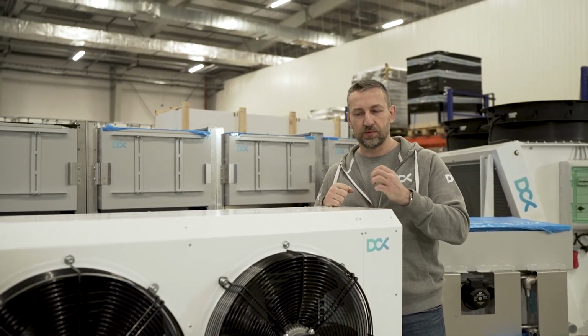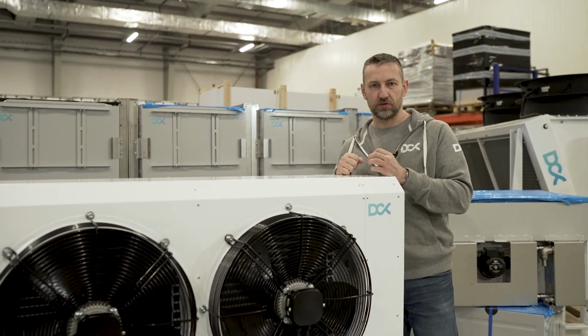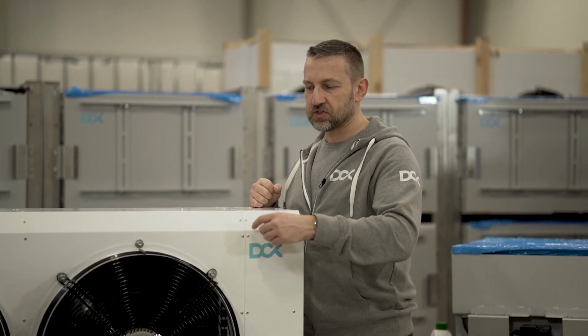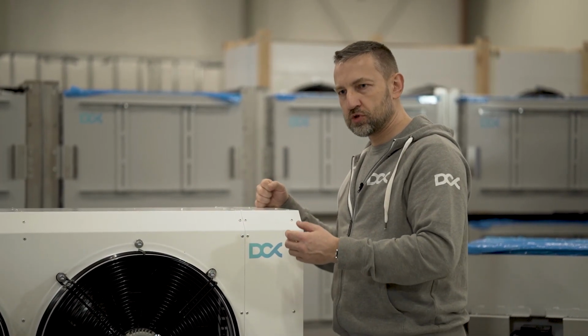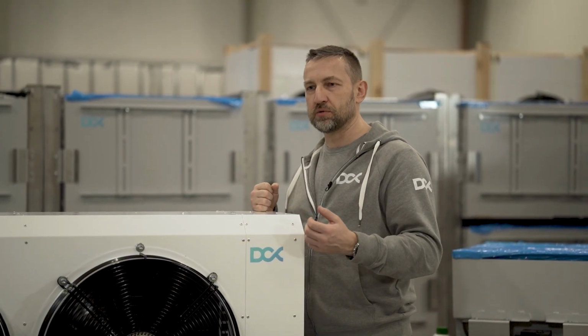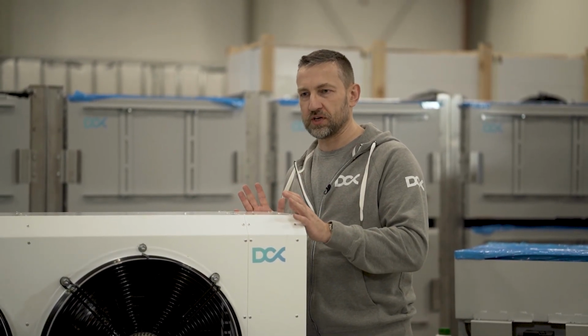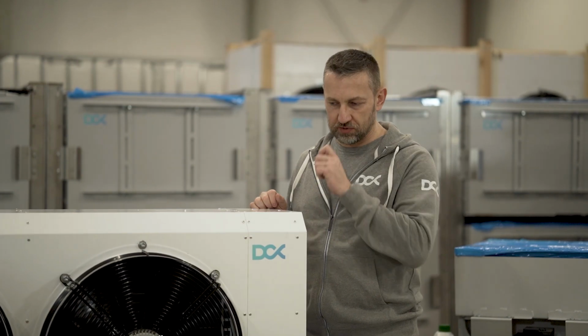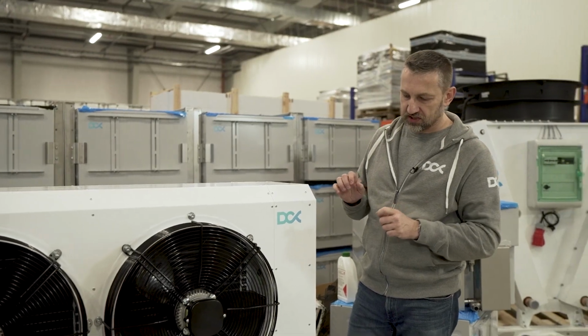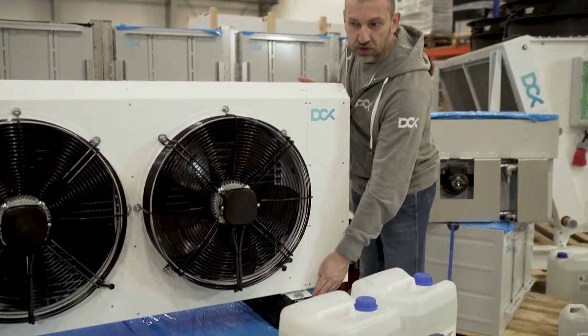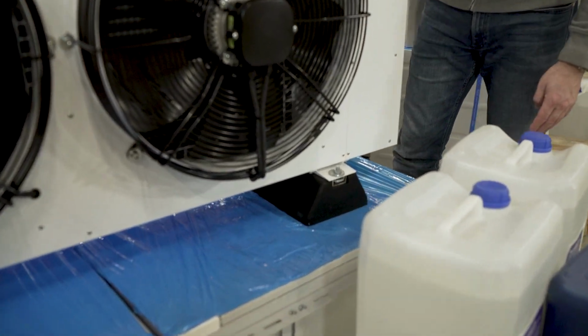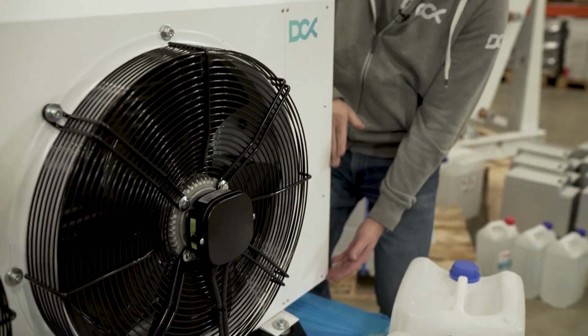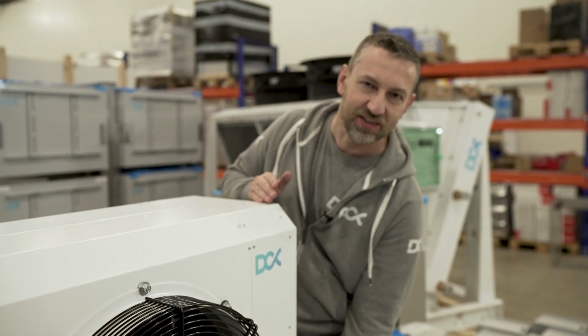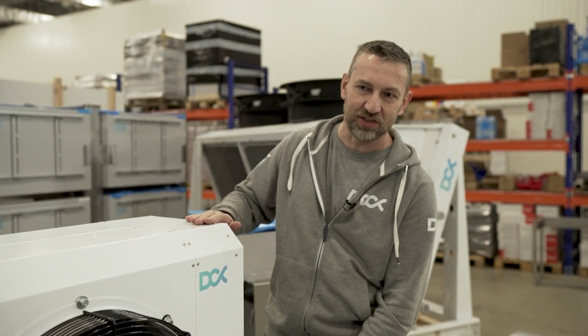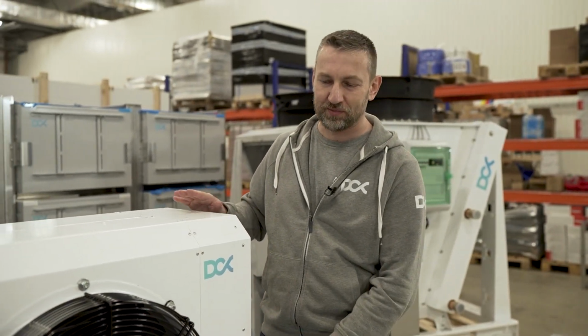It should get better heat exchange during the winter. During the winter or moderate time, the fans should slow down, or if you choose to run them at full capacity, they will allow you to overclock your miners in most areas, in most configurations. The system has two rubber legs which you need to attach. Previously we were shipping them attached, but right now we had to enlarge it. So that's kind of an oversized unit. This is the maximum which we can fit on one pallet.